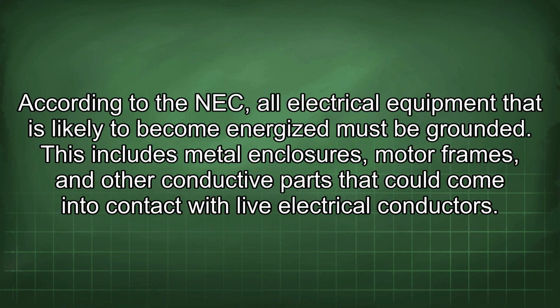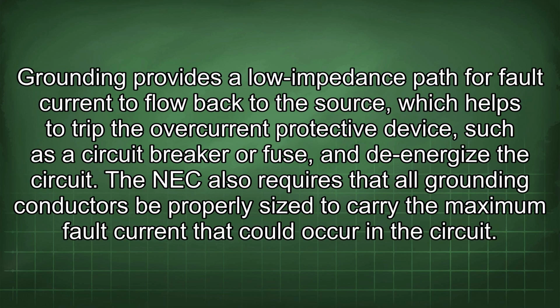According to the NEC, all electrical equipment that is likely to become energized must be grounded. This includes metal enclosures, motor frames, and other conductive parts that could come into contact with live electrical conductors. Grounding provides a low impedance path for fault current to flow back to the source, which helps to trip the overcurrent protective device, such as a circuit breaker or fuse, and to de-energize the circuit.